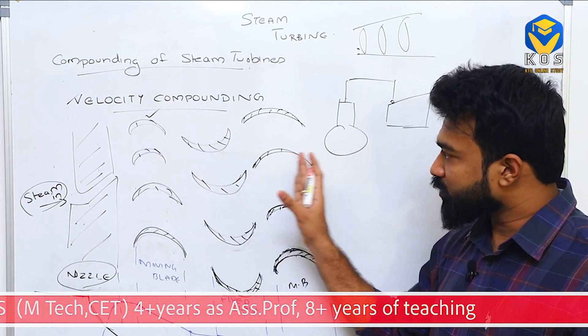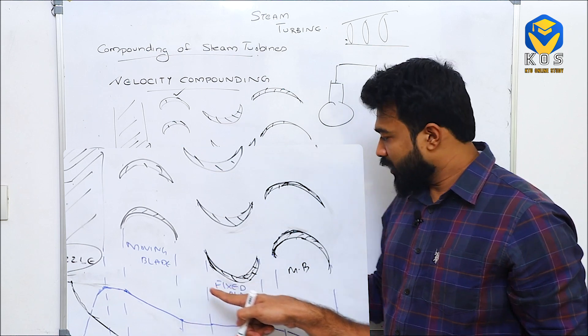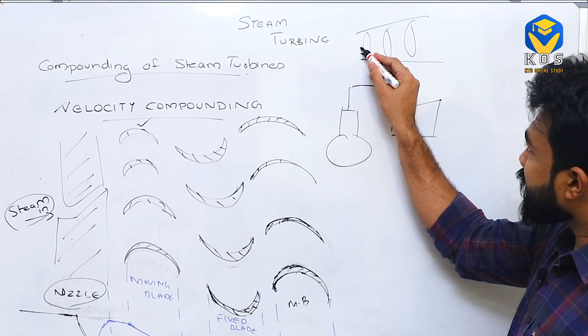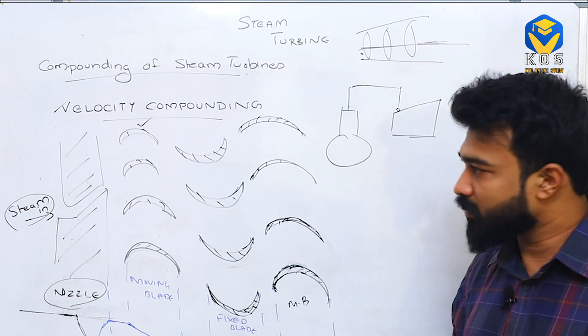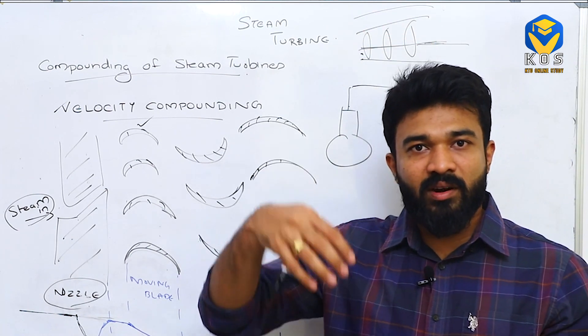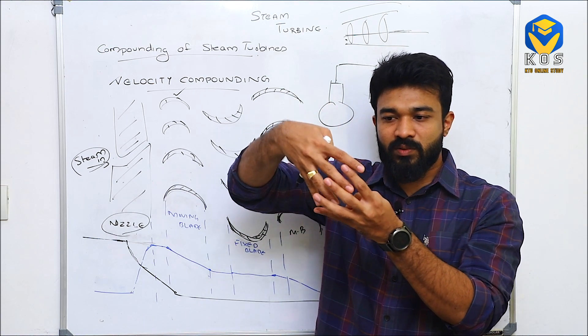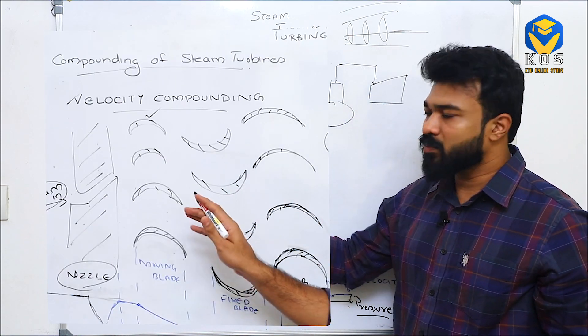We keep several rotor stages one after another. We observe one first moving blade, then a fixed blade, and again a moving blade. The moving blades are connected to a central shaft, so in one stage, the rotating steam velocity is transferred to the shaft. The fixed blades are connected to the outer casing of the turbine and do not move because they are welded to the casing.